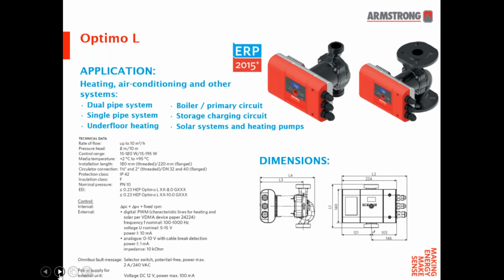And here the installation length, or the face-to-face of the body, is either 180 millimeters threaded connection or 220 millimeters flange connection. The circulator pipe connections are 1.5 inches or 2 inches. But as you can see from the center of the front face of the control, it still does have the air vent screw.